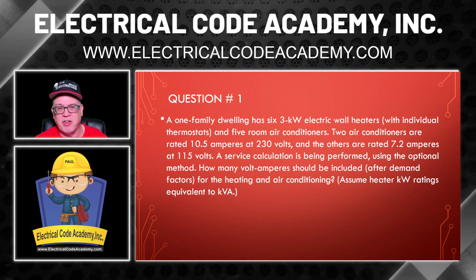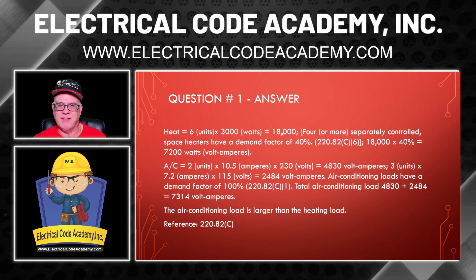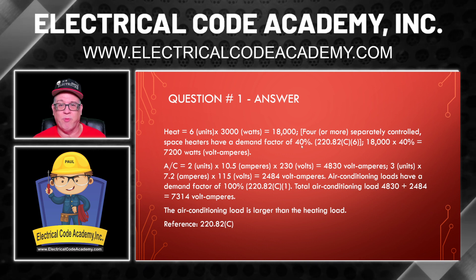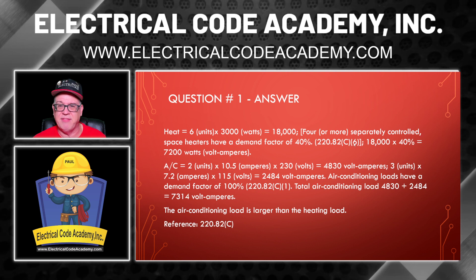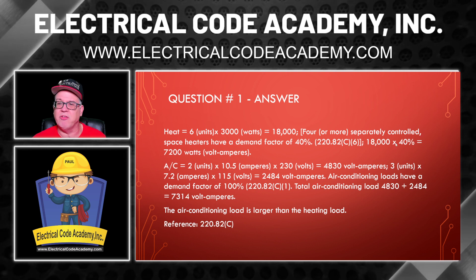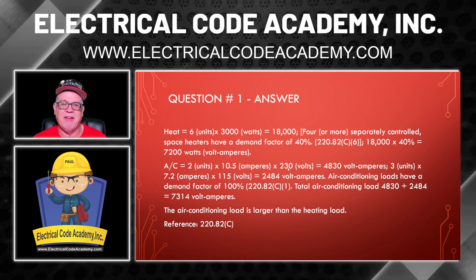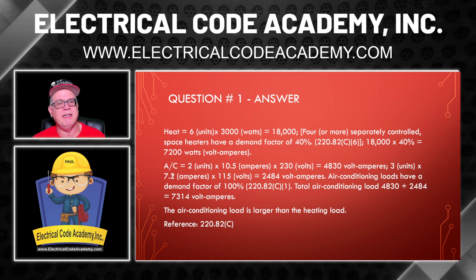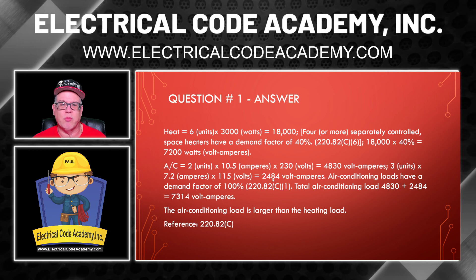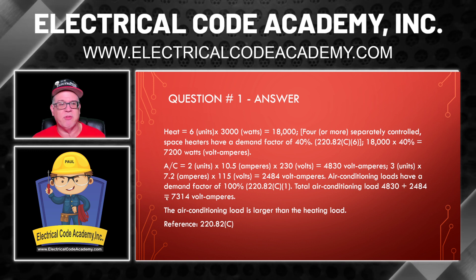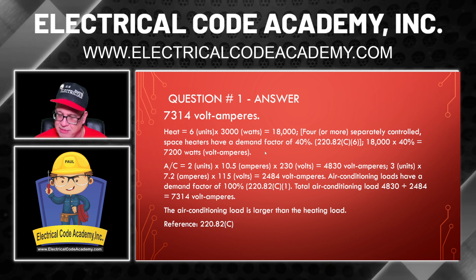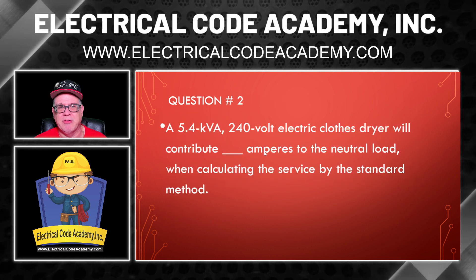Remember, it says take the larger. You thought the heat was going to win, but you were using standard-method mentality. Now we're in the optional method — we applied 40%, so it's now 7,200. The air conditioning at 7,314 VA is larger than the heat at 7,200. That's the optional method answer. So we did the six units at 3,000 each — that's 18,000 — four or more so we apply 40%, giving 7,200. The AC: two times 10.5 times 230 equals 4,830, three times 7.2 times 115 equals 2,484, total 7,314 VA. That is the larger of the two, and that's why the AC wins.